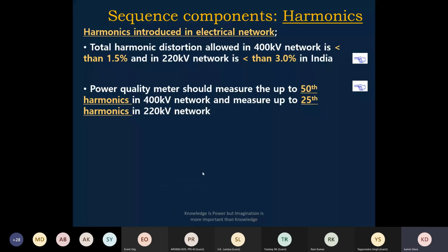ओके, टोटल हार्मोनिक्स introduced in electrical networks. So total harmonic distortion allowed in 400 kV network is less than 1.5% and in 220 kV network is less than 3% in India. Power quality meter should measure up to 50th harmonics in 400 kV network and up to 25th harmonic in 220 kV network. उतना हार्मोनिक्स अगर पावर क्वालिटी मीटर लगाया है तो उतना हार्मोनिक्स के मेजरमेंट्स की कैपेबिलिटी होनी चाहिए, 400 kV में 50 तक जाए और 220 में 25th हार्मोनिक तक जाए.